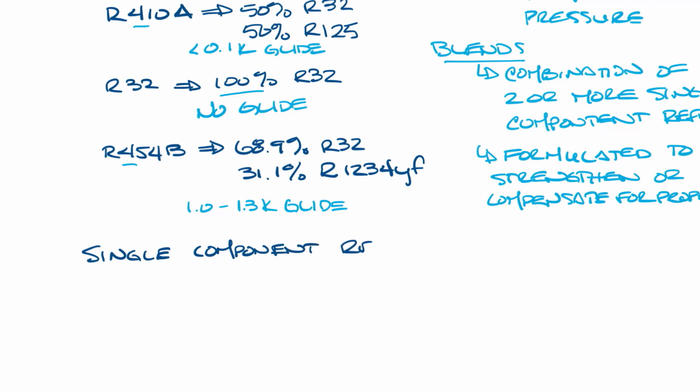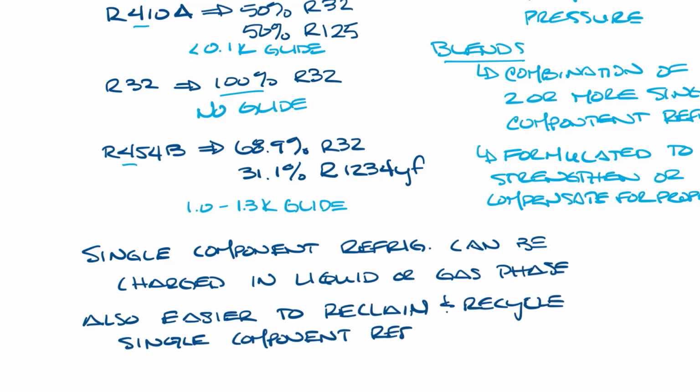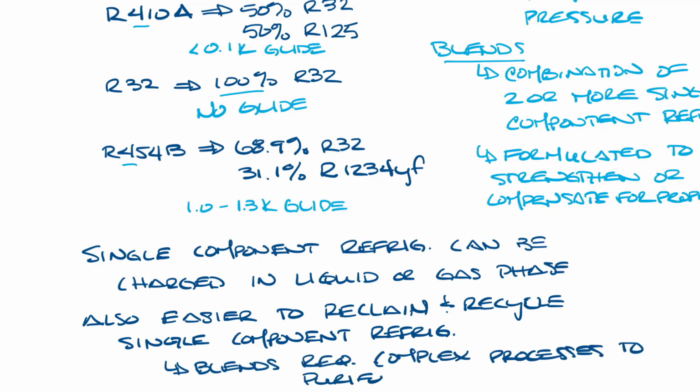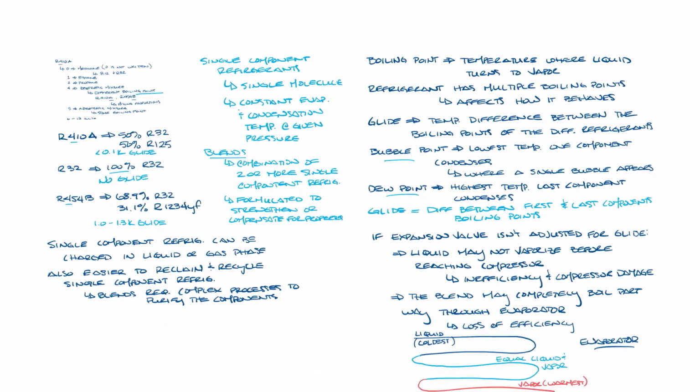Single component refrigerants can be charged in liquid or gas phase. It's also easier to reclaim or recycle single component refrigerants, because for blends, it often requires more complex processes to separate and purify the individual components of the blend.